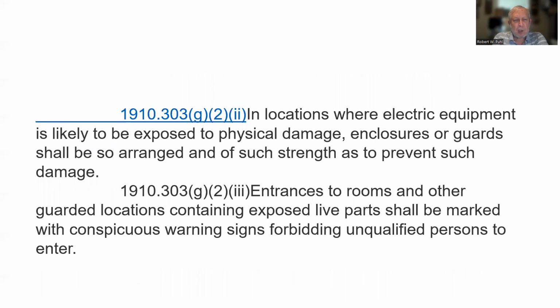In locations where electric equipment is likely to be exposed to physical damage, enclosures or guards shall be so arranged and of such strength as to prevent such damage. Entrances to rooms and other guarded locations containing exposed live parts shall be marked with conspicuous warning signs forbidding unqualified persons to enter.